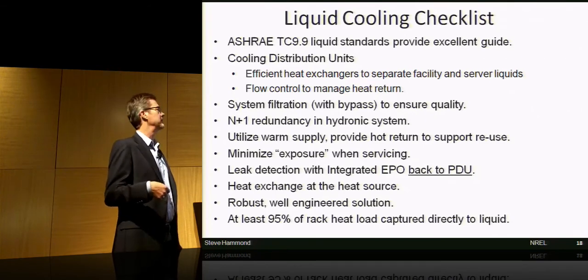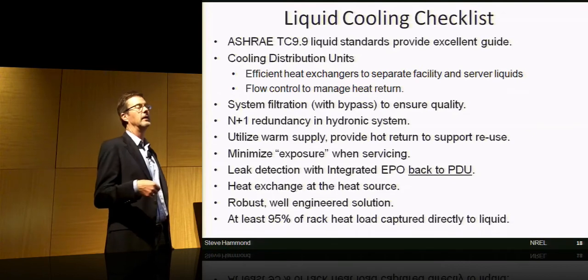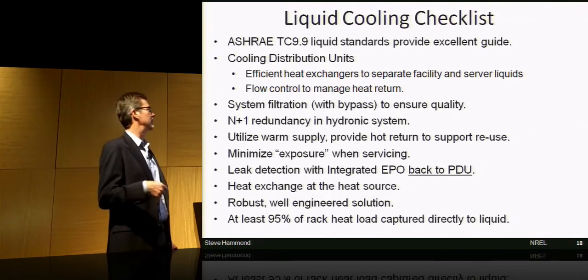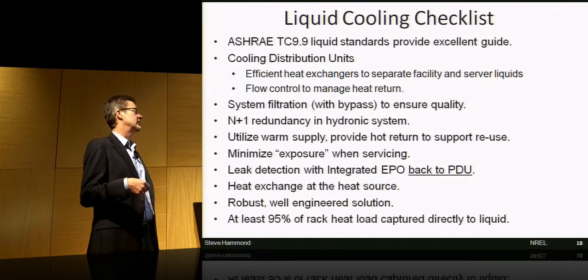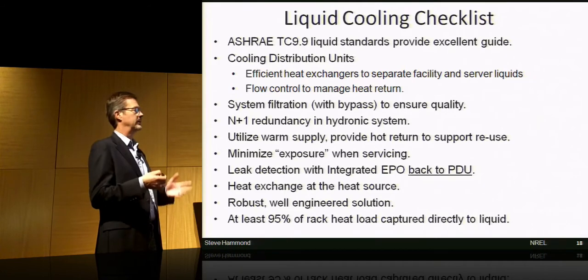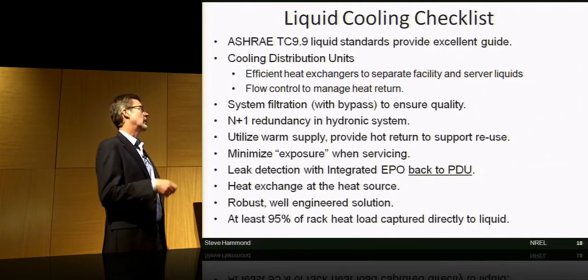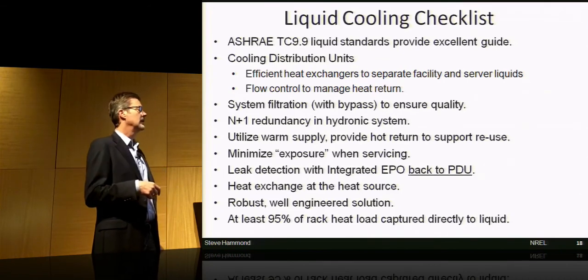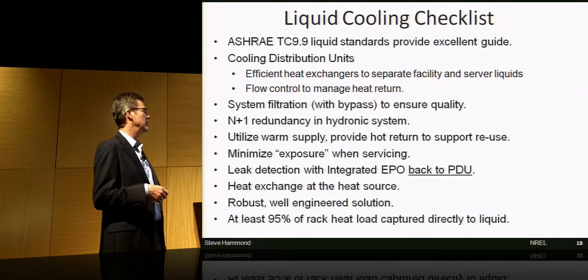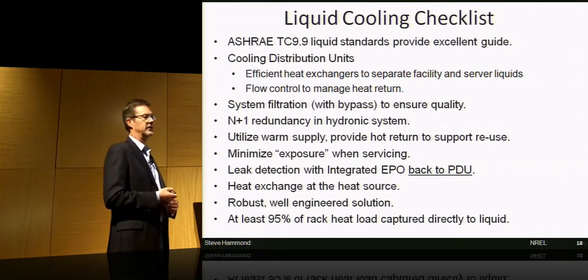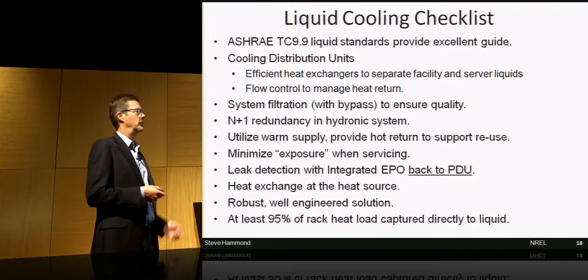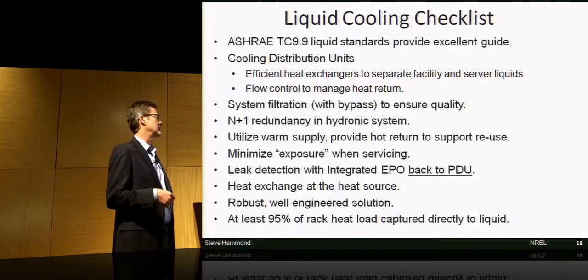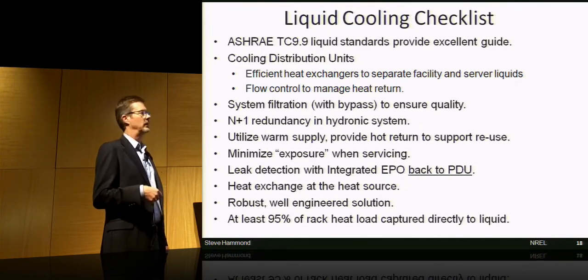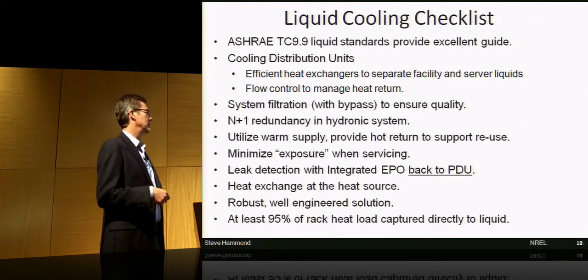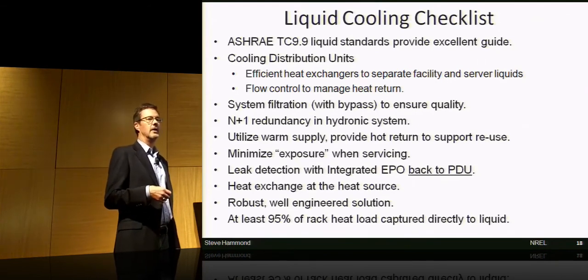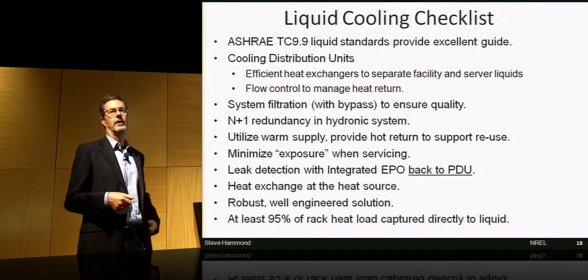If you have filtration in your system, make sure you have a filter bypass so you can change filters without having to take your system down. N+1 redundancy in your hydronic system, so that's for pumps and filters and everything else. We are utilizing warm water supply and providing hot water for maximizing opportunities for waste heat reuse. Minimize your exposure when servicing, so as Ed showed, they can service a node without breaking water connections. Do your heat exchange directly at that heat source. Look for the best, most well-engineered solution you can, and insist that you get 95% of the rack heat load captured directly to liquid. Otherwise, even though it's a liquid-cooled system, you're still going to have to put it in some sort of hot aisle containment.